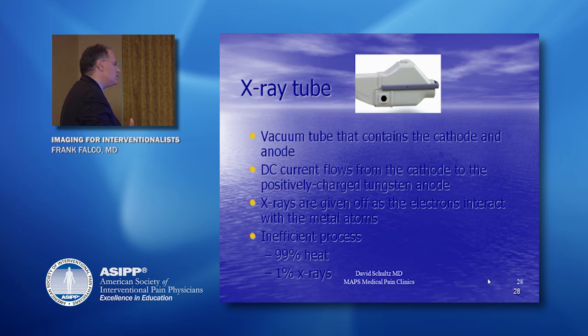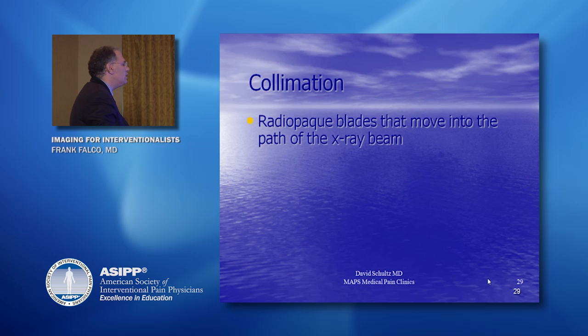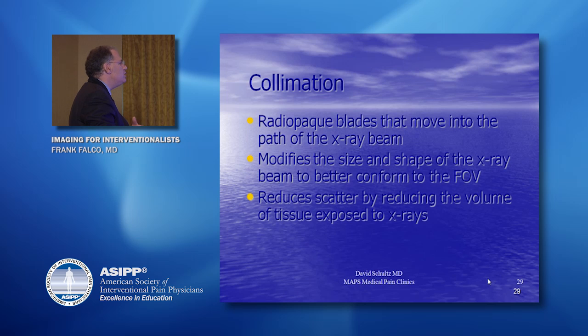It's a very inefficient process, and as you know, working with fluoroscopy, you can feel the heat coming off of the fluoroscope. So you've got 99% heat and 1% X-ray. You can use your collimators to help focus the beam. You can rotate the C-arm to also change your beam orientation. You can modify the size and the shape of the X-ray to conform to the field of view.